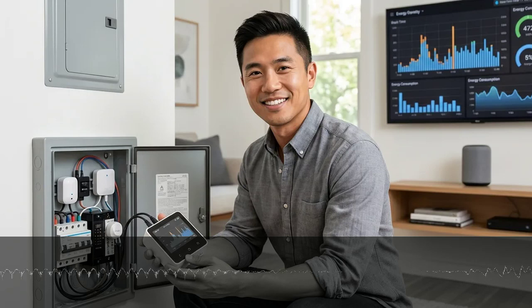Accuracy is 95 to 98% for total home consumption, 85 to 90% for individual circuits, especially ones with mixed loads, like a kitchen circuit powering both resistive and reactive devices. The limitation is that most can't identify specific devices automatically—they just show you that circuit 5 is using 1200 watts. Device disaggregation, figuring out what's actually running, requires machine learning models that need 2 to 4 weeks of training data.